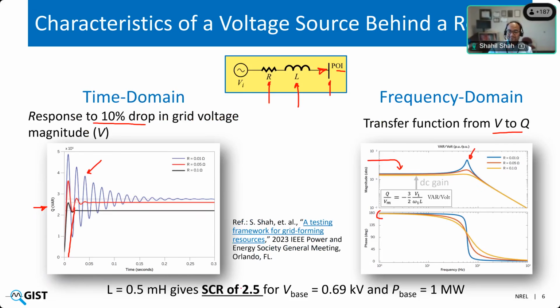Another key highlight is that if you select a voltage source behind reactor, for example this particular one, and size the reactor to provide a particular short circuit ratio, for example here it is 2.5 for the base voltage of 0.69 kV and base power of 1 megawatt, and you plot this Q by V transfer function on a per unit by per unit basis, this DC gain will be exactly the same as the short circuit ratio of 2.5. So this gives you a direct connection to how much grid strength this voltage source behind reactor is giving you. Now, if you connect this voltage source behind reactor at any POI within the grid, you would know how much short circuit ratio it is providing.